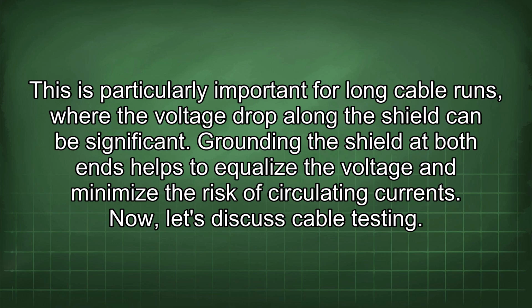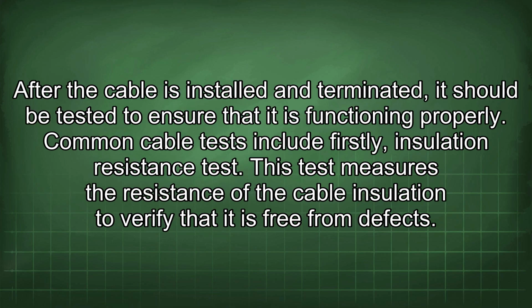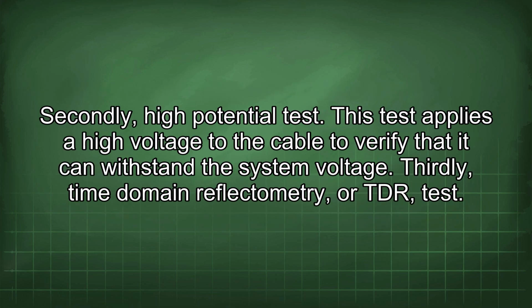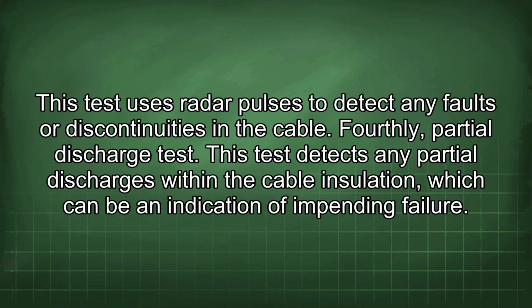Now let's discuss cable testing. After the cable is installed and terminated, it should be tested to ensure that it is functioning properly. Common cable tests include, firstly, insulation resistance test. This test measures the resistance of the cable insulation to verify that it is free from defects. Secondly, high potential test. This test applies a high voltage to the cable to verify that it can withstand the system voltage. Thirdly, time domain reflectometry, or TDR test. This test uses radar pulses to detect any faults or discontinuities in the cable.